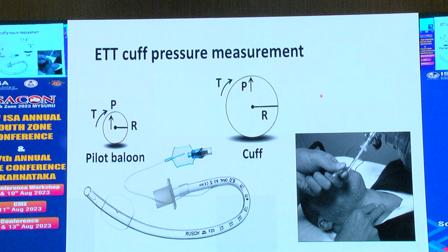or reflective of the intra-cuff pressure. So that is the reason this is not recommended. We need to use other monitors to look at the intra-cuff pressure.